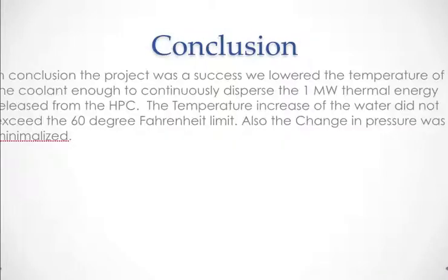In conclusion, the project was a success. We lowered the temperature of the coolant enough to continuously disperse the 1 megawatt thermal energy released from the HPC. The temperature increase of the water did not exceed the 60 degree Fahrenheit limit. Also, the change in pressure was minimized. Any questions?